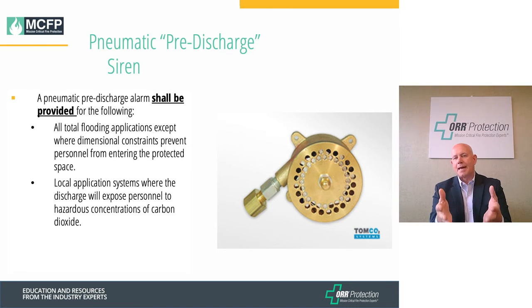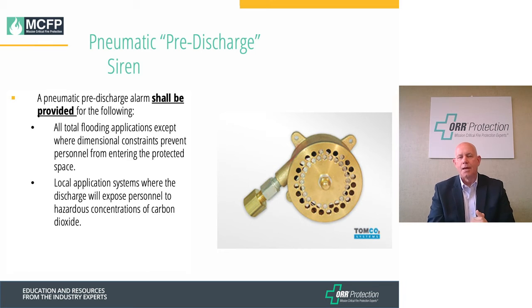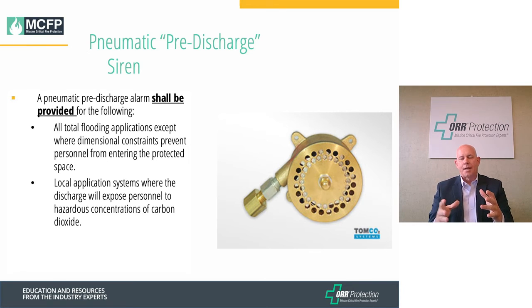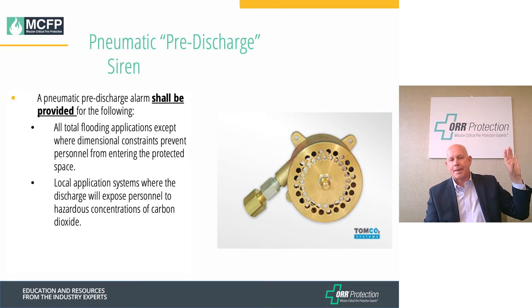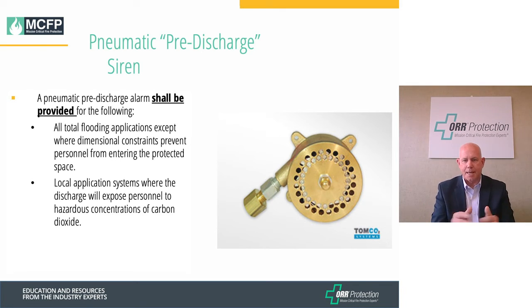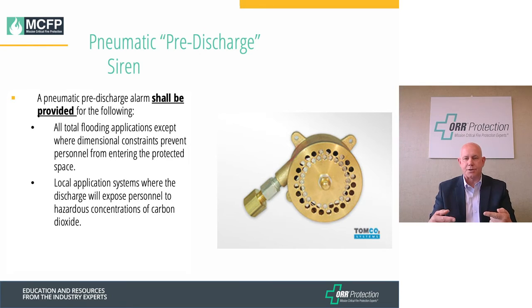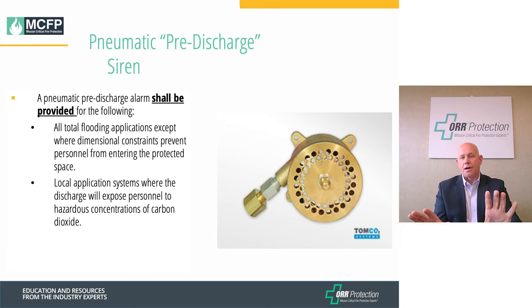Why a pneumatic siren if you already have electronic audibles? If the audible circuit is shorted out, has a ground fault, or the panel is down for any reason, someone could manually pneumatically fire the system and CO2 would discharge into the space with no audibles at all. That's why the pneumatic siren becomes so important — it will operate in virtually any condition, providing a backup warning when the electrical system fails.